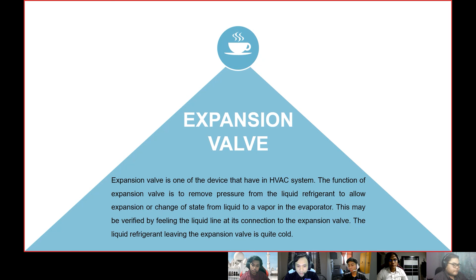Okay, I would like to present to you about the expansion valve. The expansion valve is one of the devices in a refrigeration system. The function of the expansion valve is to remove pressure from the liquid refrigerant to allow expansion or change of state from liquid to vapor in the evaporator. This may be verified by feeling the liquid line at its connection to the expansion valve. The liquid refrigerant leaving the expansion valve is quite cool.